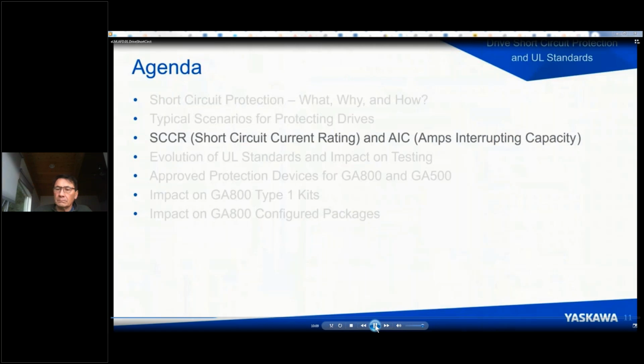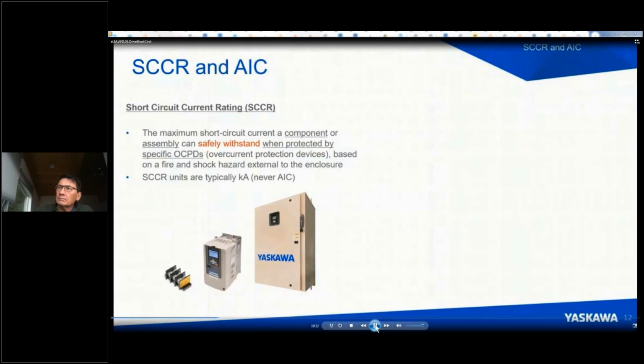So let's talk about short circuit current rating and amps interrupting capacity, because they are often confused. A short circuit current rating is the maximum short circuit current a component or assembly can safely withstand. Can safely withstand, these are very important words, and that's when protected by specific overcurrent protective devices. The units normally associated with short circuit current rating are kiloamps or amps, never amps interrupting capacity, because these are applied to components or assemblies that are not the kind of devices that would open, such as a circuit breaker or a fuse.